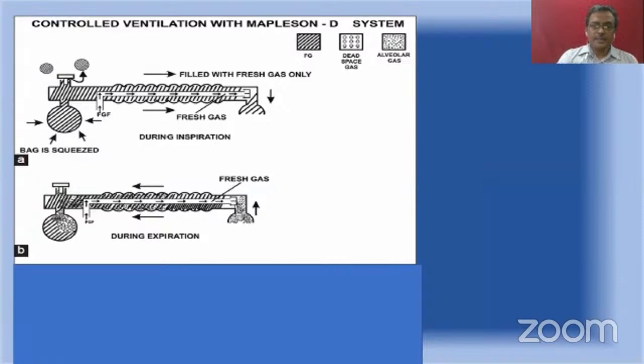Like the earlier scenario, you can see the expired gas, which contains dead space and alveolar gas, is going towards the outer tube, towards the reservoir bag, which is pushed further by the fresh gas coming through the inner tube. Can you see the inner tube? Can you see the fresh gas coming? Which is actually pushing these expired gases towards the reservoir bag.